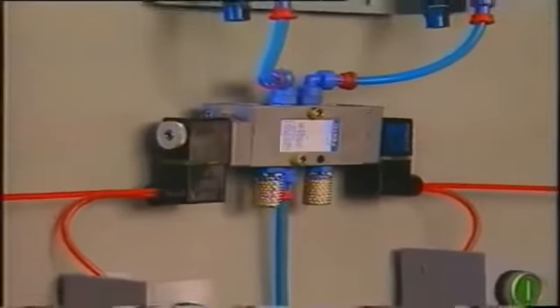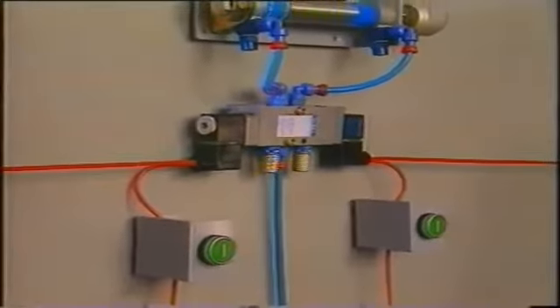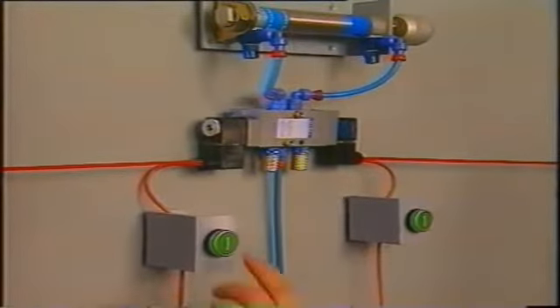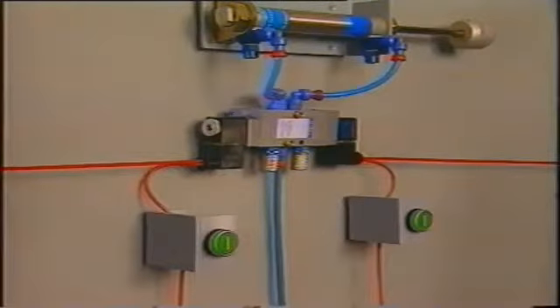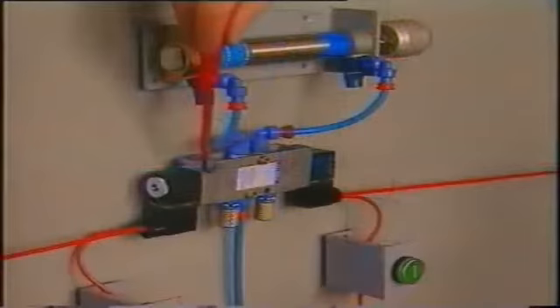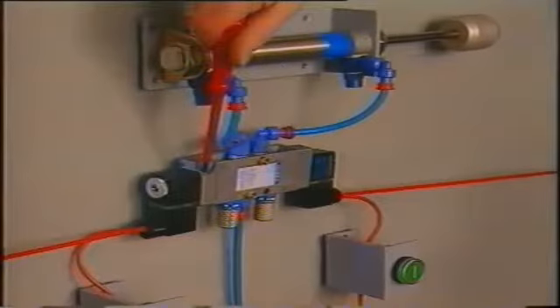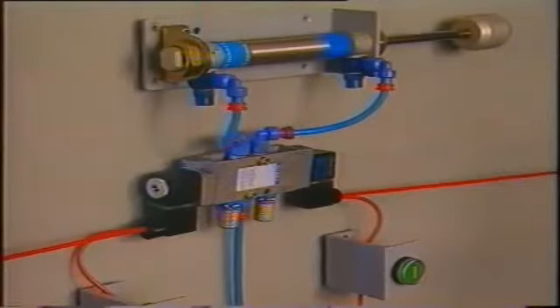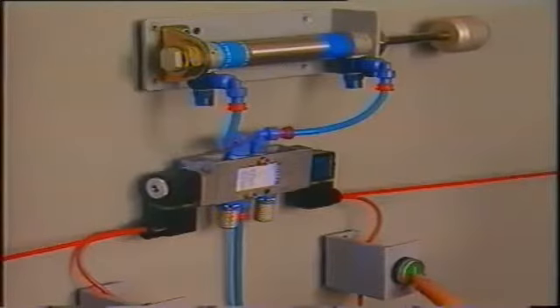Solenoid valves are normally equipped with a manual override. This allows the valve to be switched not only by the control signal, but also manually. Here, a screwdriver is being used. The manual override is used during setup of the system or for testing the function of the valve.